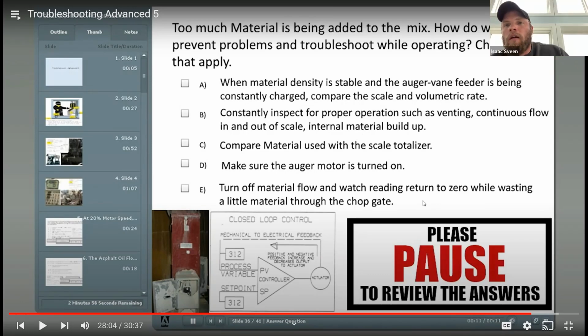I'd say A, B, and C. E is always a really good check on your scale - whenever you shut down, you always want to check and make sure your scale is going to zero. That's like checking before you step on your bathroom scale to make sure it doesn't say 20 pounds, because if it does, you can't believe what it's going to say when you step on it. Okay, that makes sense.